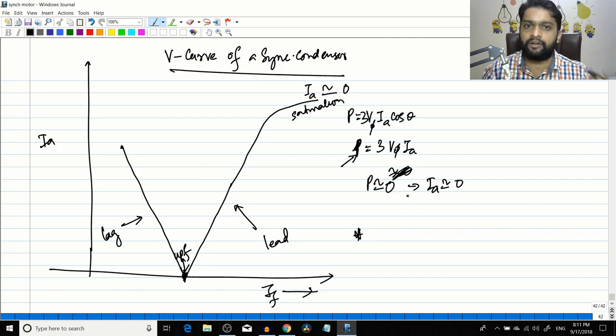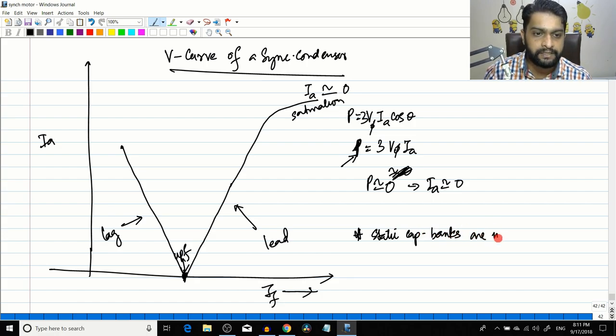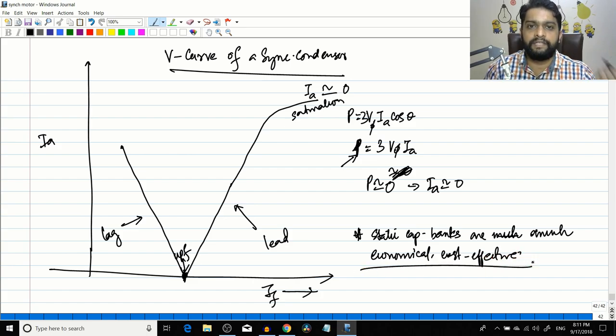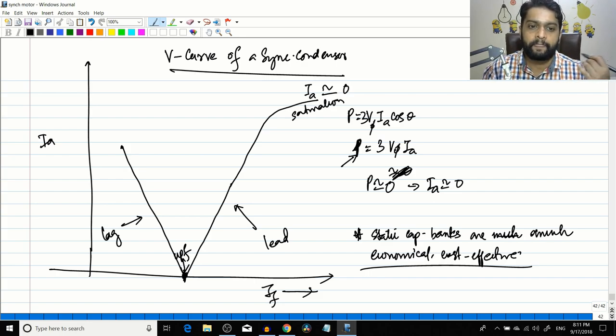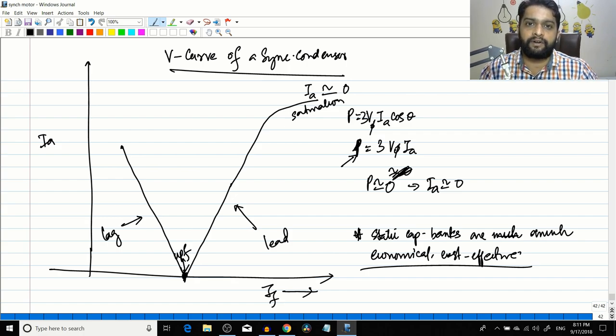Nowadays synchronous condensers are not much in use because static capacitive banks are much more economical and cost-effective. You don't have the hassle of installing a synchronous motor - synchronous motors are rotating machines. Nowadays capacitive banks are much cheaper compared to installing a synchronous motor. So today we saw a device called a synchronous condenser, which is basically an over-excited synchronous motor under no-load condition.